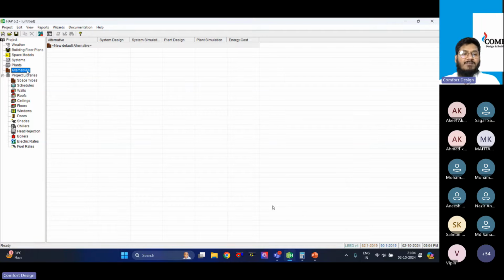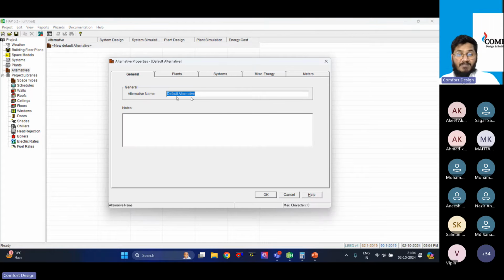You have an alternatives option where you can give an alternate plant if you want. For example, if you know your building heat load will be around 200 to 300 TR or 150 to 300 TR, you have two options: a VRV system or a chilled water system with chillers. So you can create an alternate HVAC system, proceeding with both VRV and chilled water. I chose chilled water for the previous version, but now I can choose VRV as well.